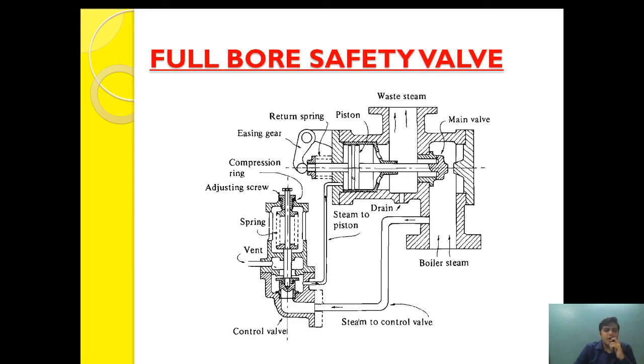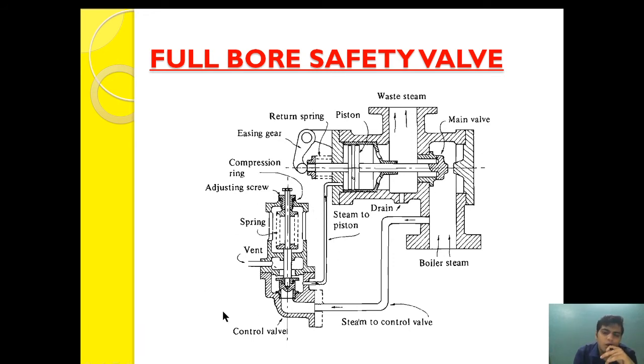Now let's see the design of the full bore safety valve. As you can see, this is the boiler steam which escapes through the valve passage. There are two valves: one is the main valve and the second is the control valve. The steam pressure is acting both on the main valve and through a steam control line it is also acting on the control valve.